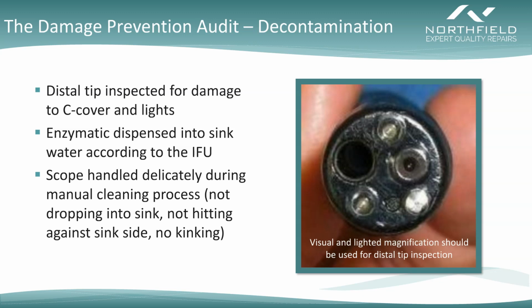Now, also during this process, the scope has to be handled delicately. That means not dropping it into the sink, not accidentally banging it against the sink side, no kinking, no wrapping it up very tight. It's very easy to make these mistakes as a reprocessing technician and not realize it. So again, this is a great advantage of having somebody who is auditing this process, because they can watch and see when mistakes are happening that the actual person performing the reprocessing may not even be aware of.